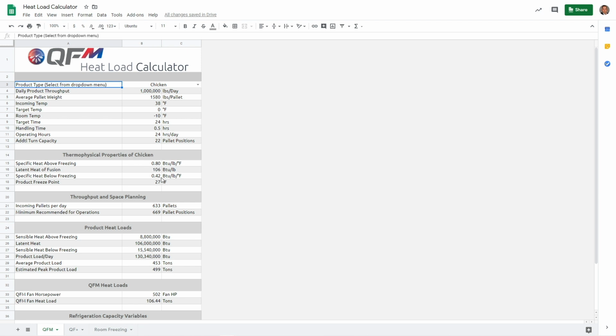That figure, 0.8 BTUs per pound per degree. Then our latent heat of fusion for chicken is 106 BTUs per pound. And the specific heat below freezing, 0.42 BTUs per pound per degree. And the expected freeze point of the product, 27. Those are all values from the lookup table after we put the chicken in as the product.